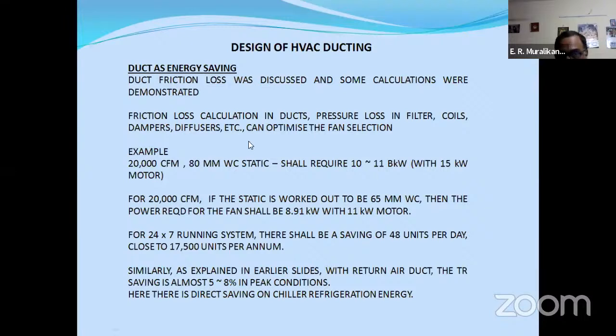Now, duct design energy saving. We discussed the friction loss and some calculations were demonstrated. You know how important the velocity is, because if velocity is higher, friction loss is higher. Friction loss higher means BKW higher. Then fan model, everything adds on and adds on. Calculating friction loss in ducts and pressure loss in filters and coils can optimize the fan selection.